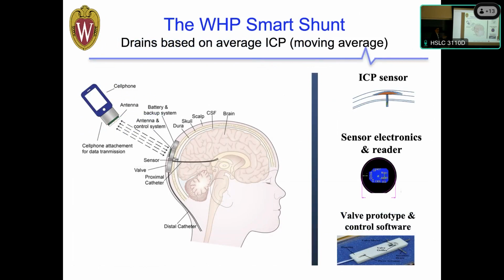So from this, the WHP team put together a set of engineers, scientists, and physicists, and we designed a smart valve system that has an ICP sensor, electronics, and a valve that is closed all the time, except when you ask it to open. It works based on a moving average: over 3 or 4 minutes, it averages the ICP, gets rid of those instantaneous pulses, and then if it's above a certain level, it opens for however long you want it to open, and then it closes.